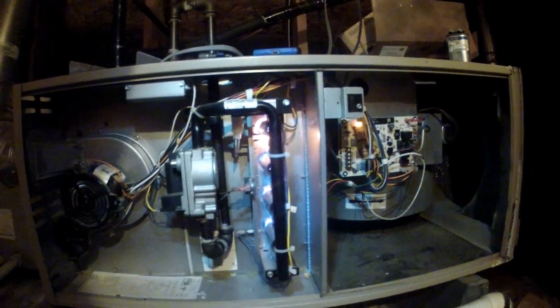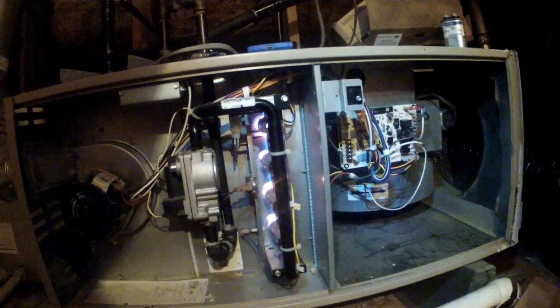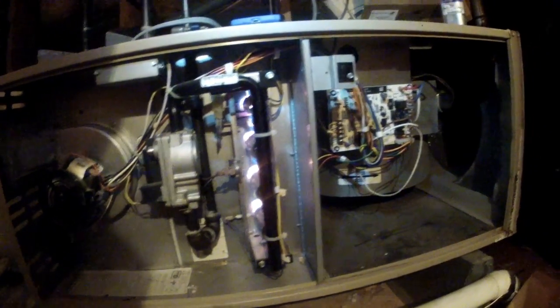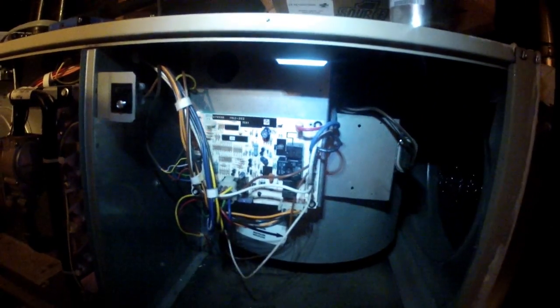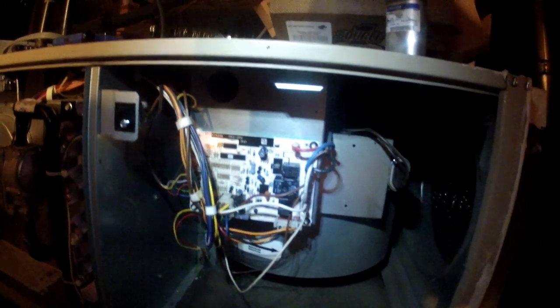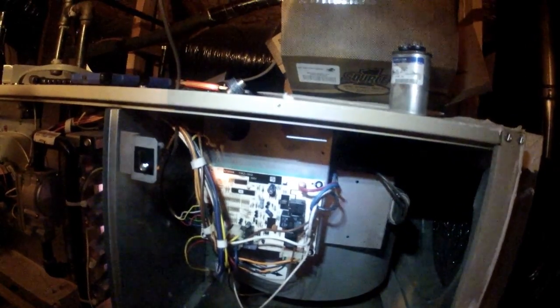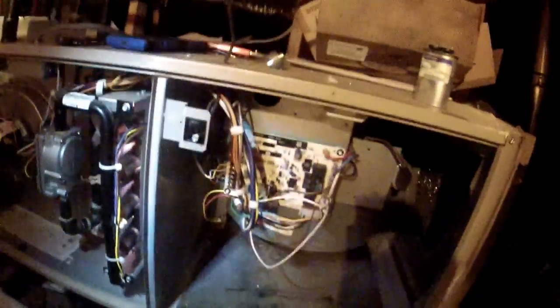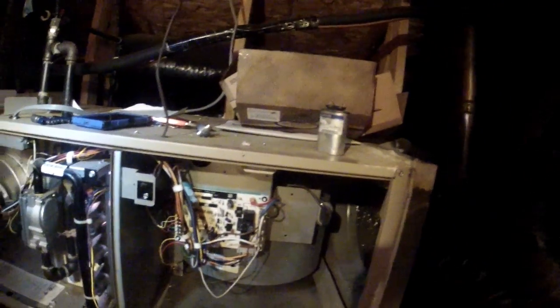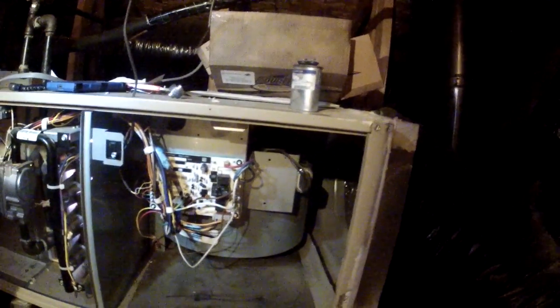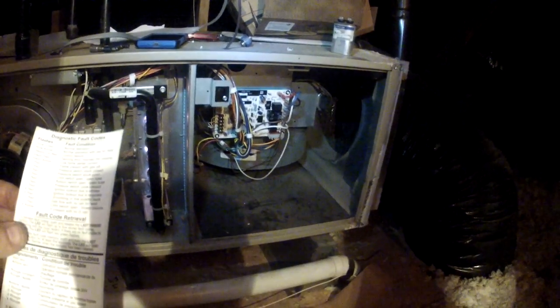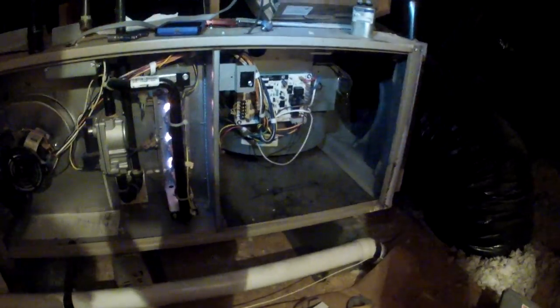Inducer started. Hot surface igniter. Gas. Flame sensor is sensing. Crazy flashes from the board. Saw rapid amber lights flashing, so on here it means that there's low flame sense current. So let's make sure we clean the flame sensor before we leave. But otherwise everything starts up.